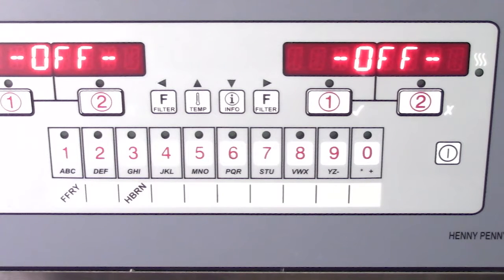So always think of our supply voltage for our main burn on our gas valve as coming from our ignition module. Okay, so the first thing we want to check then is going to be our oil levels. We have to get the input from our temperature probe. That's going to tell our control board that we're seeing a rise in temperature, or a rate of rise in temperature in a certain amount of time, and if not, you'd get the E22 error code.